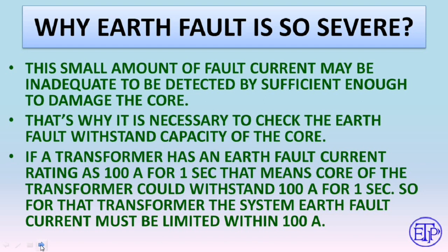Every machine with a core, like a transformer or generator, has an earth fault current rating. For example, a transformer may be rated at 100 amperes for 10 seconds — meaning the core can withstand 100 amperes for that duration. The system earth fault current should be restricted to this rating. Before installing any transformer or NGR (neutral grounding resistor) system, we must ensure the maximum earth fault current carrying capacity of the core and restrict the earth fault current within that capacity.